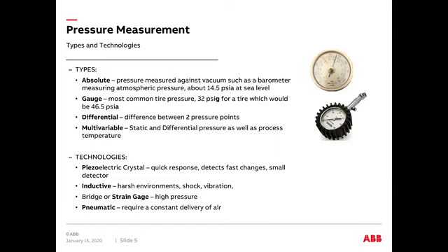And then there is differential pressure. On differential, you're measuring the difference between two different pressures, and that's the reading you're getting. Now the multivariable is another one, and it includes measuring the difference between pressures, one of which is static, and it also measures the process temperature. So that's the different types of transmitters.